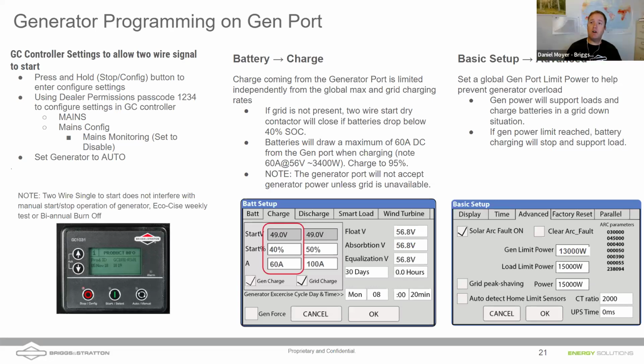Yeah, thank you, Nathan. And then on the far right is what we're looking at. That's where we're going to come into that advanced tab and be able to adjust the maximum amount of watts we're going to want to pull on the generator. That's going to prevent you from overloading your generator. And so, Nathan, this one overrides the one in the middle. Is that correct? That is correct. So if we are looking at a generator limit power, there are a couple of things we can do. First, we could set the generator limit power so that we don't overdraw the generator. And then we can also go into the Solarc and set the Solarc to prioritize loads first if we have too small of a generator.